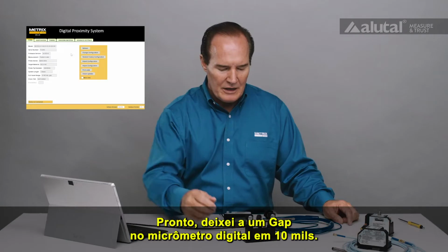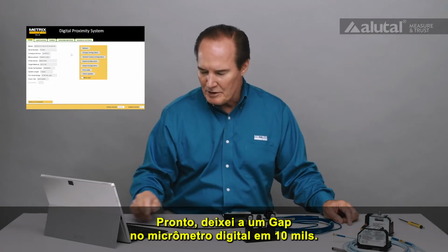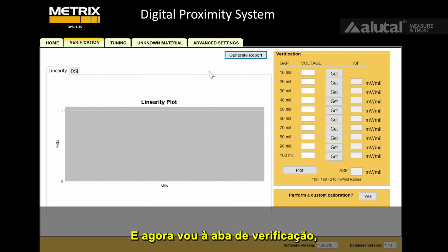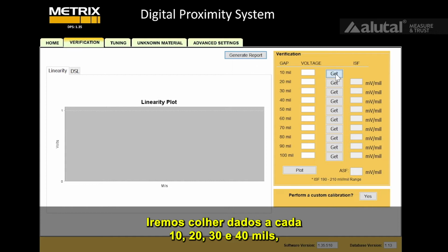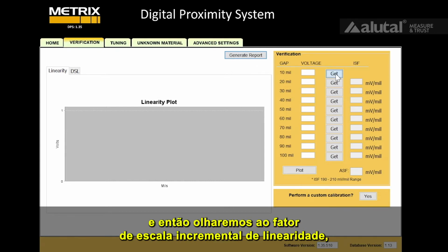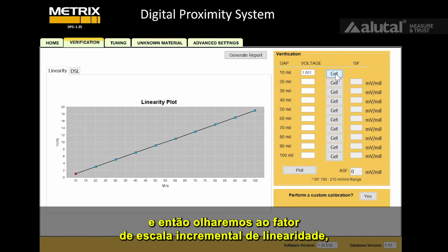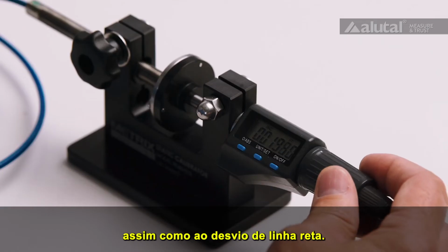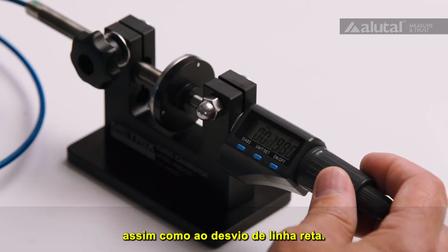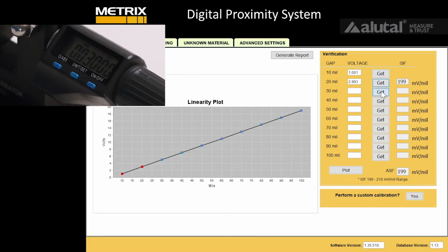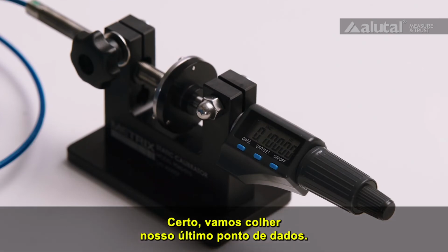All right, I've gapped the digital micrometer to 10 mils, and now I'll go to the verification tab, and we'll take our first data point. We'll take data every 10, 20, 30, and 40 mils all the way to 100, and then we'll look at both the linearity, incremental scale factor, as well as deviation from straight line. All right, then we'll take our last data point.